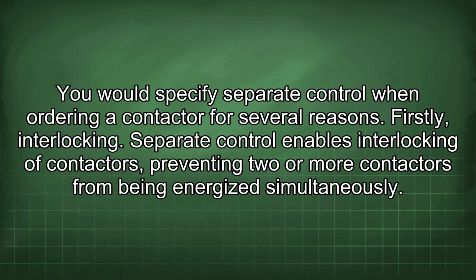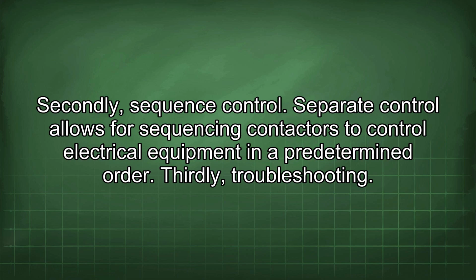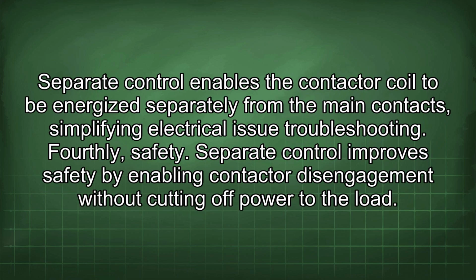Firstly, interlocking. Separate control enables the interlocking of contactors, preventing two or more contactors from being energized simultaneously. Secondly, sequence control. Separate control allows for sequencing contactors to control electrical equipment in a predetermined order. Thirdly, troubleshooting. Separate control enables the contactor coil to be energized separately from the main contacts, simplifying electrical issue troubleshooting. Fourthly, safety. Separate control improves safety by enabling contactor disengagement without cutting off power to the load.